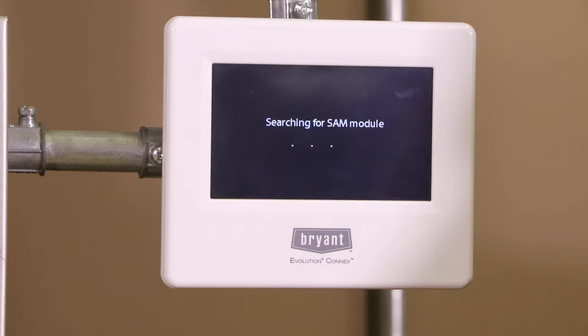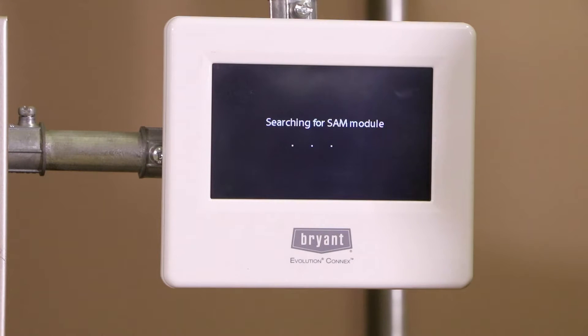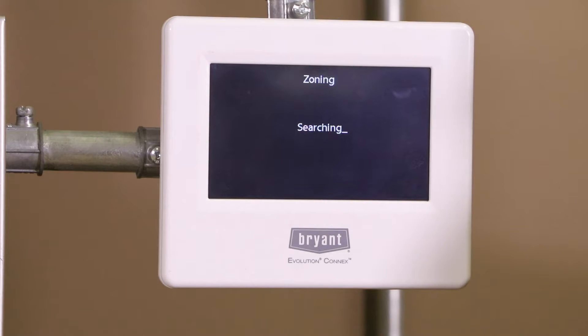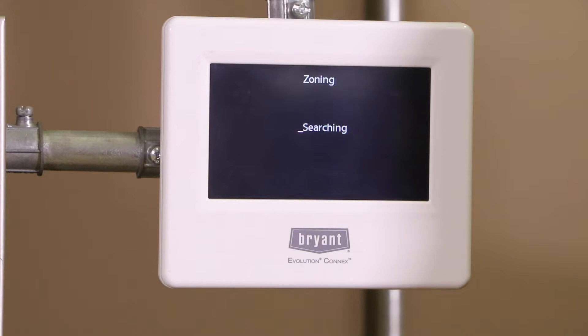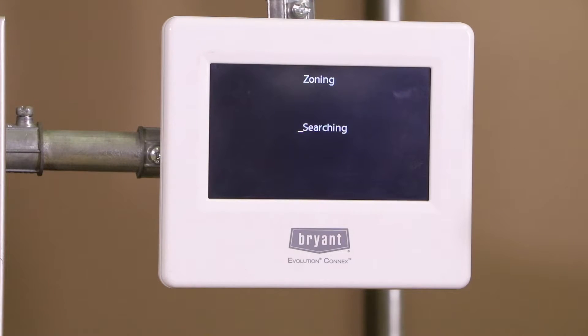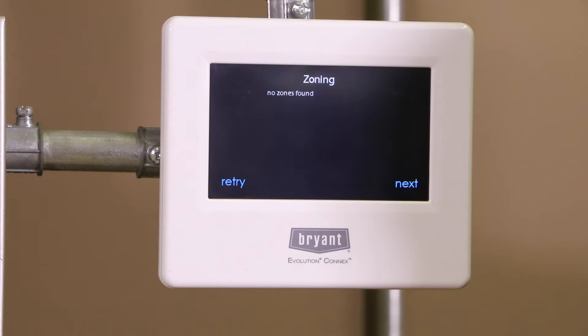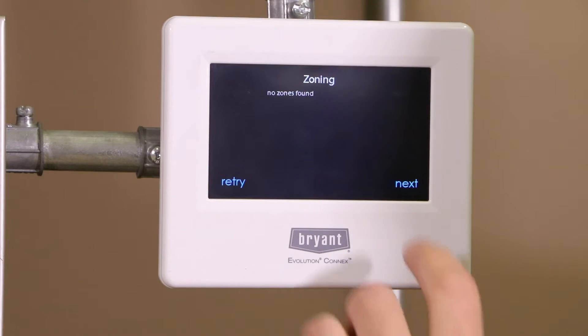Now it's searching for different accessories that we may have on the system. We don't have other accessories on this particular system, so it's not going to find a zoning board, an ERV, or any of those communicating devices. It's still searching for a zoning system — in our case today it will not find one, but if it did, it would set up the zoning panel for us. No zones found, which is what we'd expect — we have a single zone system.